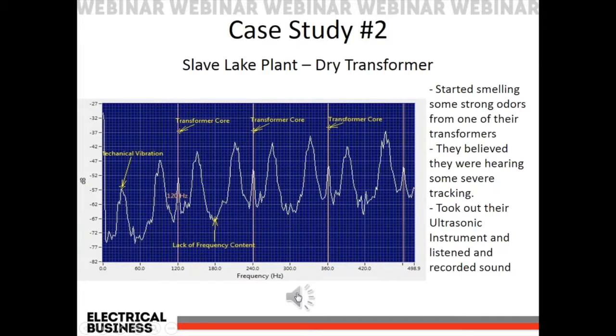So another technical issue today. Basically, the sound was much like the mechanical looseness that we heard before, and you can see in the spectrum there that what we're getting is some vibration coming from these big harmonic peaks here, and that's from the vibration that was occurring in there. But look what's in between those things: 120 hertz showing up. That 120 hertz on that dry transformer again indicated that there was a core issue in there. In other words, there was an issue with the core that was causing the vibration.